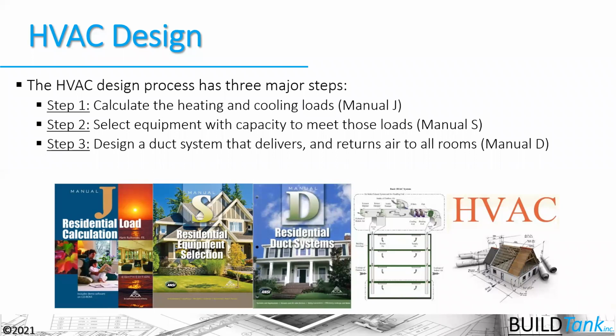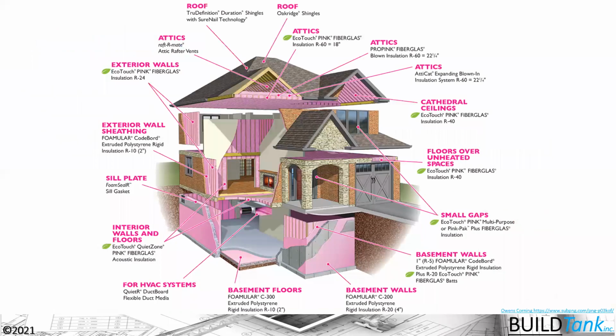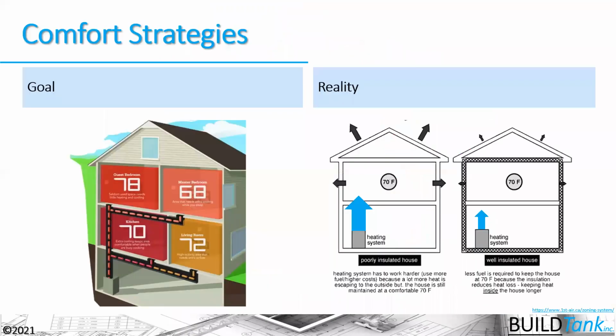Now, this process, especially step one, again, is using those assumptions about the thermal envelope and what R-values are being created or used around that building envelope to separate conditioned space from unconditioned space. And the assumption is that those R-values are going to be installed so that they're actually achieved in that building thermal envelope. Because ultimately, our goal in an HVAC system, in conjunction with that thermal envelope of the home, is to create a house that has even temperatures from room to room and floor to floor. But the reality is out there that that thermal envelope might not be working as well as we hoped it would be. So we end up oversizing the equipment to compensate for that.